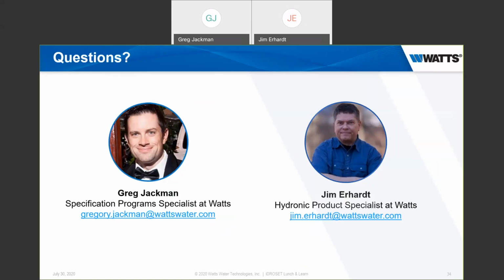Okay, the face of the units, will they show GPM or LPM? Great question. They will show GPM. Remember at the beginning of the presentation, I said this was a product that was developed in Europe for the European market. It's been on the market there since last year. In Europe, they use British pipe thread. That's why you see those union style nuts on there. The British pipe thread is a straight thread. It seals on the end of the pipe as opposed to a national pipe thread that actually seals on the threads.